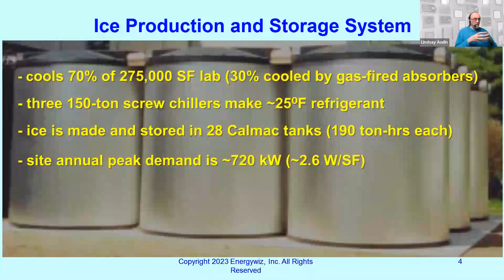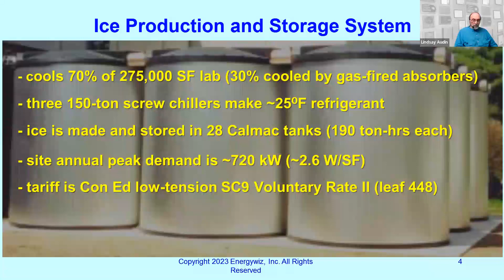For those who are trying to figure out how this is all done through the tariff, it is Con Edison low tension SC9 voluntary rate 2. For those who are following along in their tariff, it is leaf number 448. Bottom line, it's a voluntary time of day rate you can get if you have thermal storage in your system. However, this kind of tariff, which is ideal in some ways for thermal storage, has 3 separate summer peak demand periods. There's a peak demand period between 8 a.m. and 6 p.m., 8 a.m. to 10 p.m., and one for 24/7.